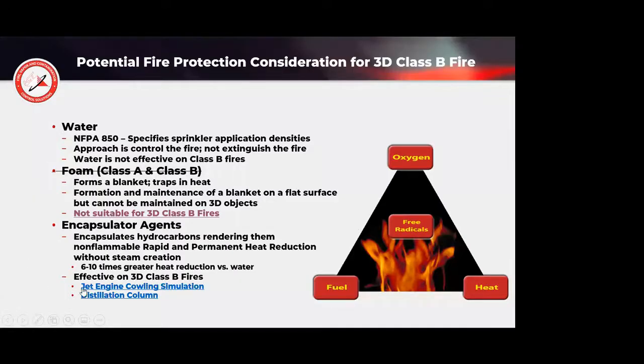We see high expansion foam systems used a lot because it's pretty well understood that I'm not going to be able to blanket this unless I have a total flooding high expansion system. So sometimes when we see those systems used for these three-dimensional Class B type fires like a transformer, I often shake my head because the base standard for foam says it's really not suitable for that. I didn't create the standard. It just kind of surprises me. Where the encapsulator agent is very suitable for that.